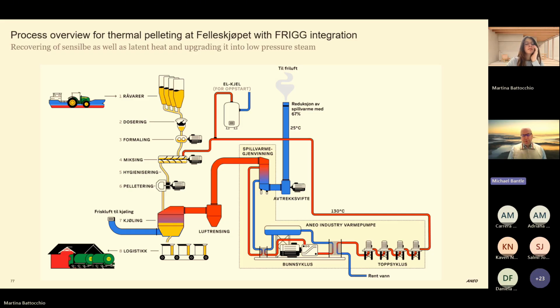Then we take this energy in the form of a water cycle and put it in our heat pump with an ammonia bottom cycle. From there we upgrade it to around 80 to 90 degrees. There we generate steam, and then we compress the steam up to around 1 bar G, plus a certain amount of superheat, and that is then injected back into the mixer, thereby substituting the current boiler.